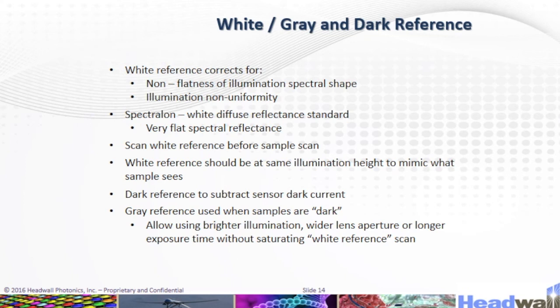White, gray, and dark reference: The white reference corrects for non-flatness of the illumination spectral shape and illumination non-uniformity. Scan the white diffuse reflectance standard — which has very flat spectral reflectance — before the sample scan. The white reference should be at the same illumination height to mimic what the sample sees. Use the dark reference to subtract sensor dark current. A gray reference is used when samples are dark, allowing the use of brighter illumination or a wider lens aperture or longer exposure time without saturating the white reference scan.